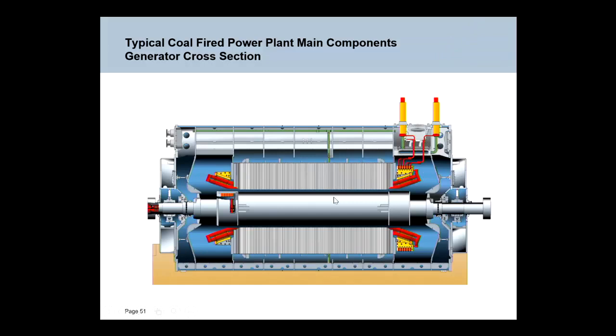Okay, and this thing is spinning at 3,000 RPM on a large coal unit. This generator will be filled with hydrogen. The hydrogen cools the generator, and the windings will be at something like 20,000 volts. So it's also quite interesting technology. It's sealed with oil, so the hydrogen stays in, so it doesn't get out to atmosphere and burn, hopefully. And everything in here is at 20,000 volts.